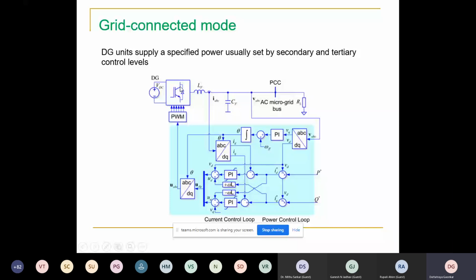Another thing you need to know: as per the grid code, whenever the inverter is in grid connection mode, it should be able to control the active power. It does not control the voltage and frequency, which is the responsibility of the grid. Whenever it gets islanded, you need to control voltage and frequency because the grid will not be there. You have to feed the loads with constant voltage and frequency. So the power electronics interface requires two separate control strategies, and you need to switch over.